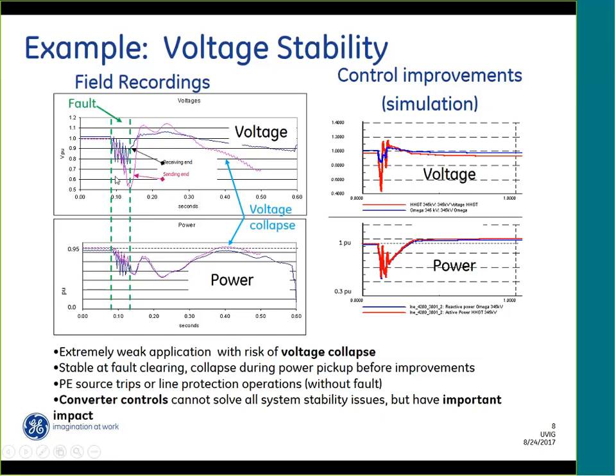A fault occurs, and the fault is then cleared. During the fault, you see this behavior where the sending end voltage tends to go down quite a bit. This is as a consequence of the fault. This looks like an oscillation, but it's not really an oscillation. It's the effect of the negative sequence in these RMS calculations. So an important aspect of the fault time is that during the fault, the voltage was low. The wind turbines, in this case, saw the low voltage, and as a consequence, they reduced the active power. That's a control action. When the voltage is low, the turbines tend to reduce the active power. And this is to help stability during the fault.